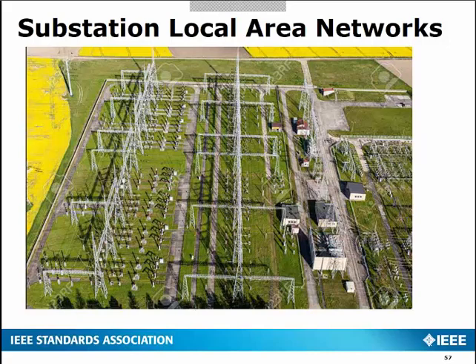In a substation, in particular a large substation, there's hundreds of data being sampled at very high rates that requires precise timing for the algorithms of IEDs to correctly operate. So it's very important that we have accurate time, not just over a wide area, but locally within a large substation.